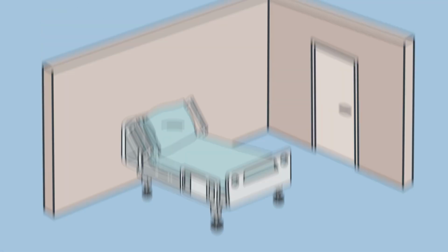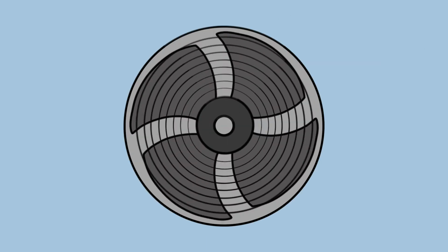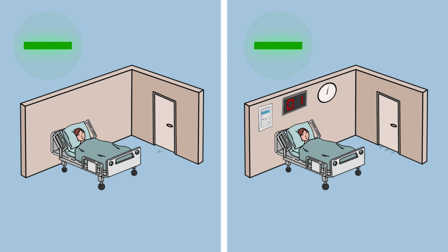In healthcare facilities, there are a few reasons to convert a room, area, or space from positive or neutral pressure to negative pressure. Each time you convert an area to negative pressure, you will need to take several factors into consideration. The first factor to consider is choosing the right-sized fan to ensure your facility's objectives are met. The objectives might be as simple as achieving negative pressure, or they might be to achieve negative pressure following the Airborne Infection Isolation Room, or AII room standards.